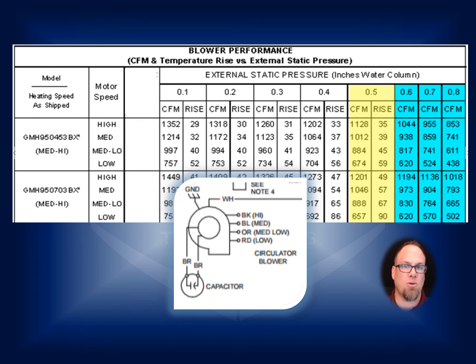So to sum up what we can fix and what we can do with our ducted systems to provide better airflow: one, you go out there and you look at a job, and you're bidding a job and putting in new equipment, or even on a service check, look at the return air drop. You can get a lot of information from the return air drop. Is it physically sized right? Is it big enough for the return air on the new equipment? Do we have adequate filter space, meaning, is it at least 16 by 25 or bigger?